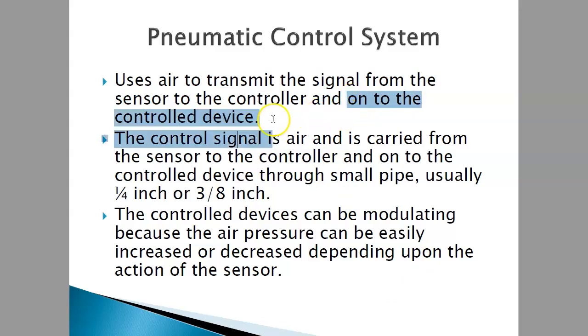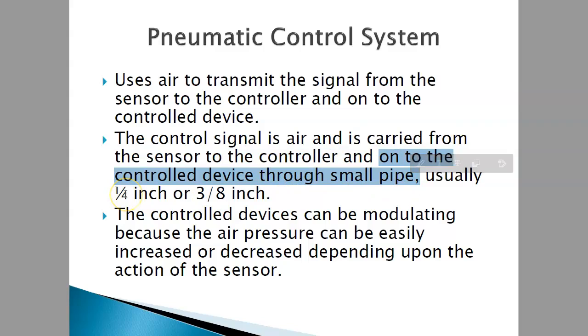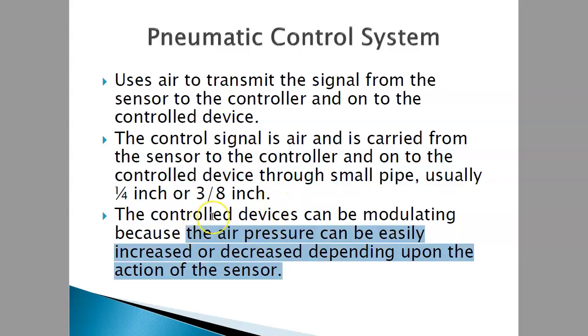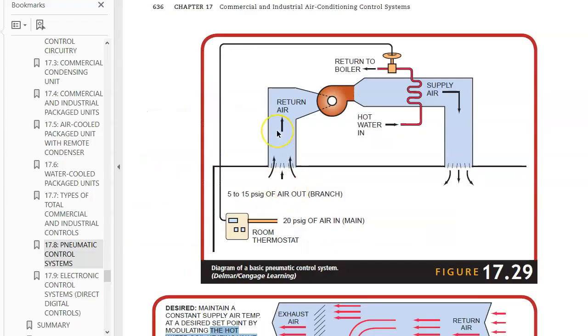For the control device, I will send you a YouTube video so you can see the pneumatic control device. The control signal in the air is carried from the sensor to the controller and onto the control device through a small pipe, usually 1/4 inch or 3/8 inch. The control device can be modulating because the pressure can increase or decrease depending on the sensor. This is a diagram of a basic pneumatic control system.